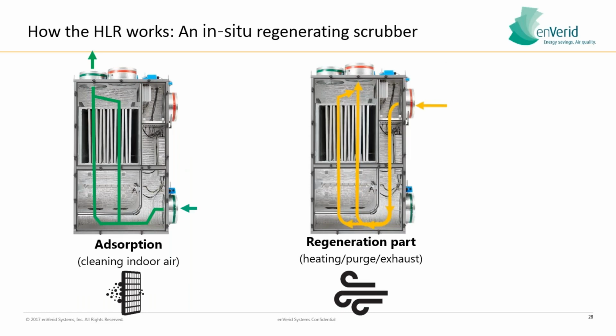Now I mentioned the regeneration process. CO2 is so prolific within buildings and indeed the environment that eventually it will saturate our cartridges. So just as a precautionary measure, typically on a daily basis, we will put the unit into standby mode, okay? Typically when the building's not occupied, or if it's a 24/7 application, we'll do it during times of low occupancy, or we'll operate on an N+1 methodology with 2 devices where one's regenerating and one's still operating.